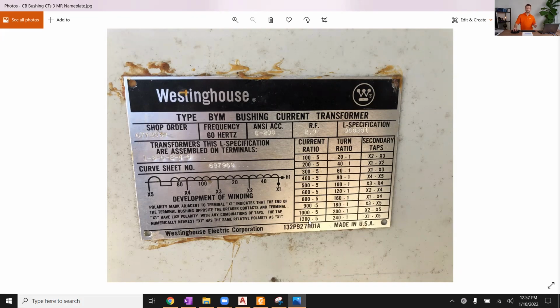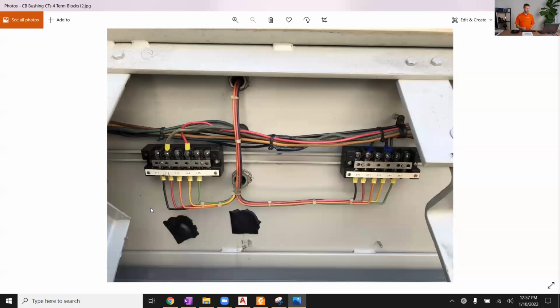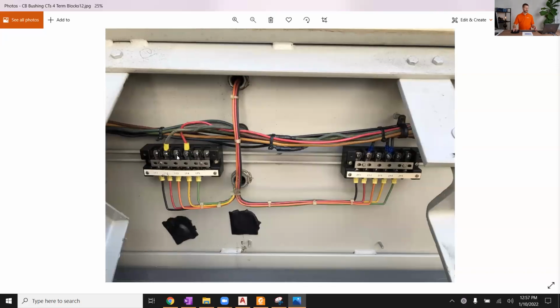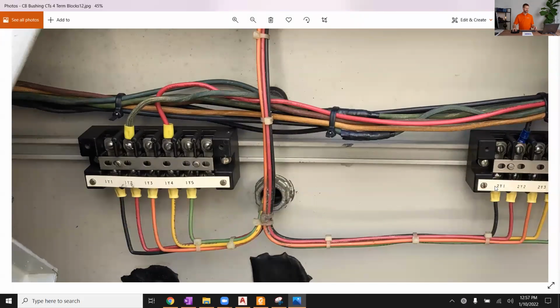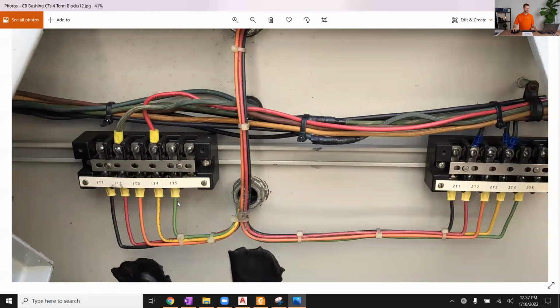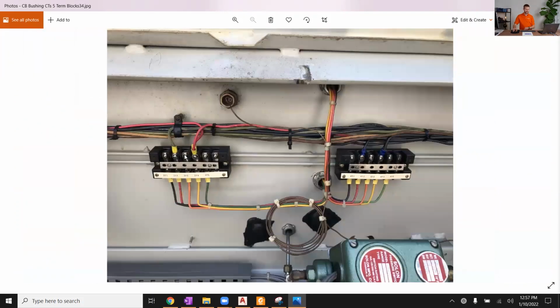So if we wanted a 600:5 CT ratio, we would use the X2 to X4 taps. We would wire from the X2 to the X4, and that would be a 600:5 CT ratio, versus if we went X1 to X5, that's full tap, that's a 1200:5 CT ratio. We'll look a little more at that later, but here are some pictures of those actual CT terminal blocks in this old breaker. This is the 1 and 2 bushings. There's the 5 taps brought in, X1 to X5. And notice it's 2 to 4. So this is a 600:5 ratio for this particular relaying application.